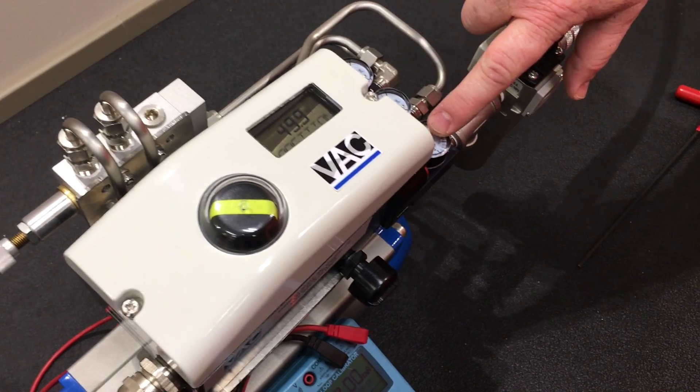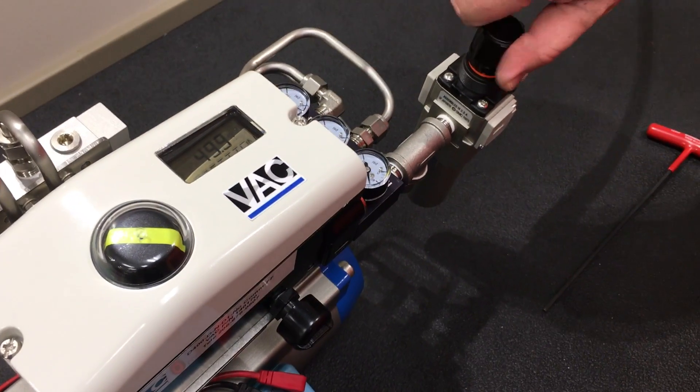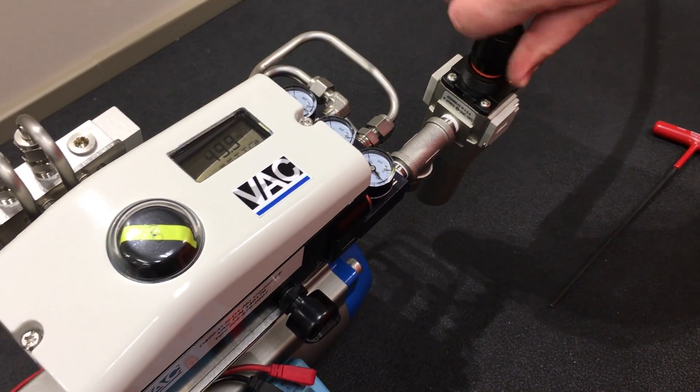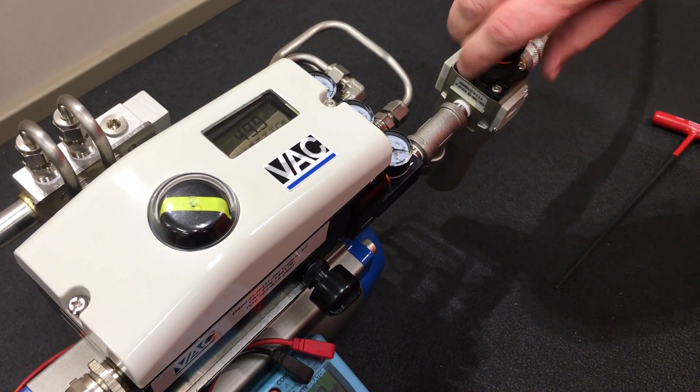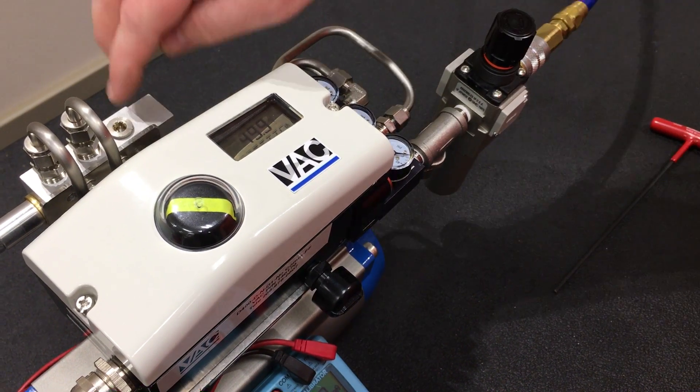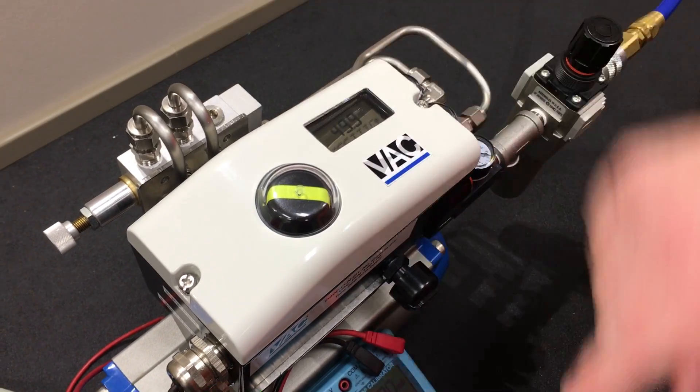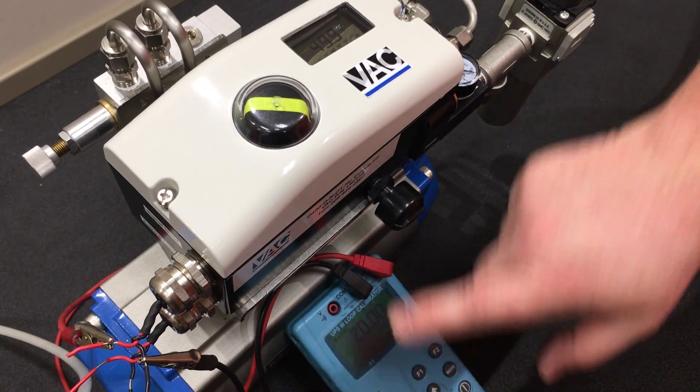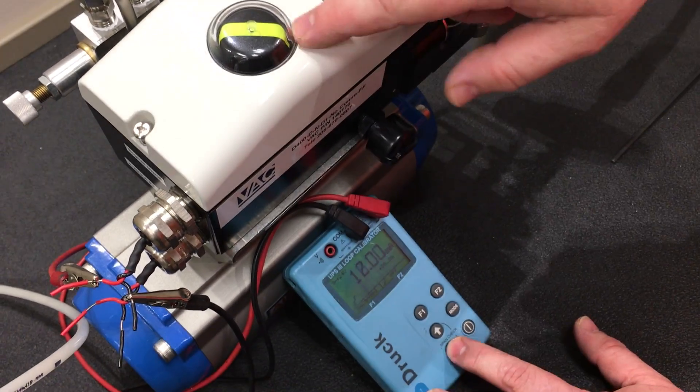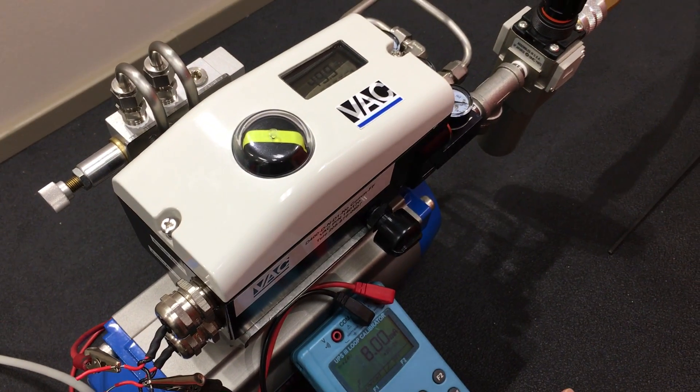We will simulate by dropping air pressure. Now the lockup valve has locked all ports closed. We will change the signal and we'll see that no matter what signal we give it, there is no change in position.